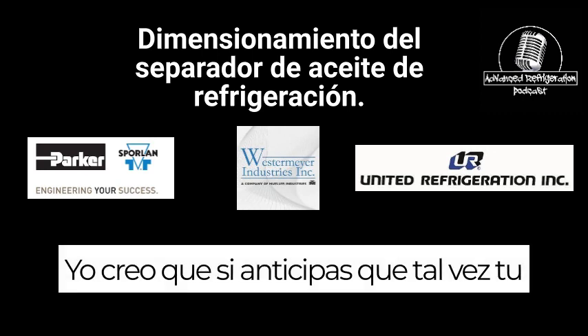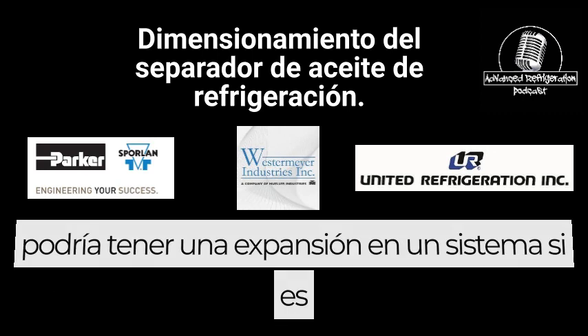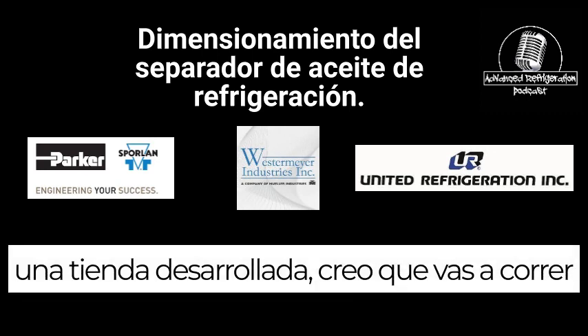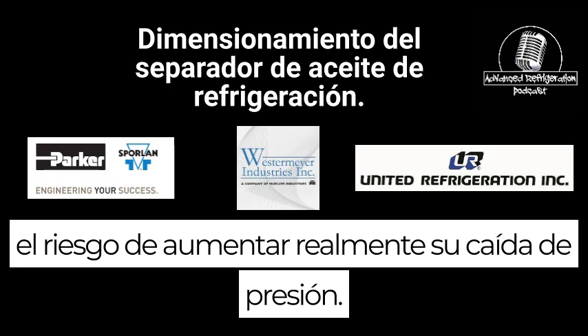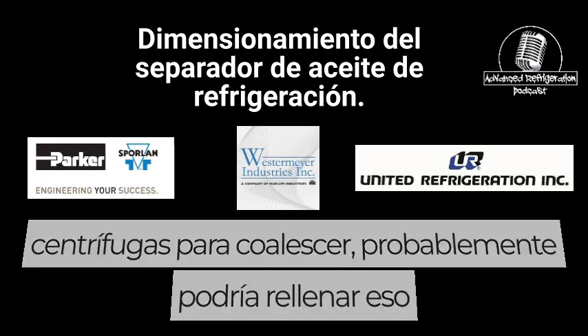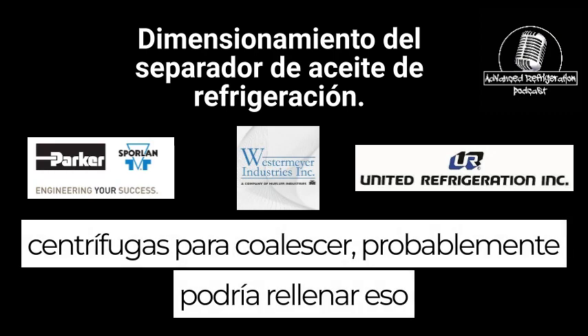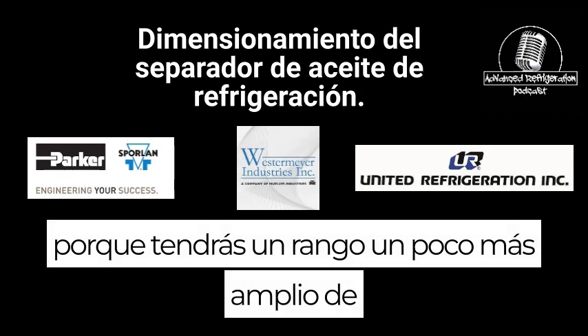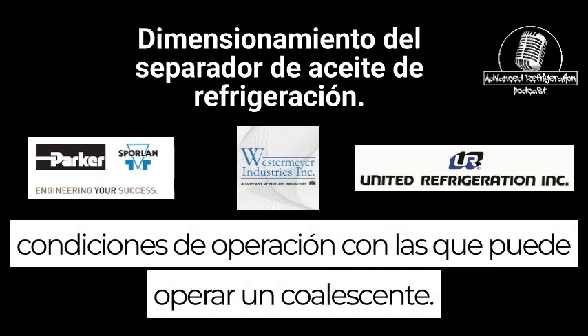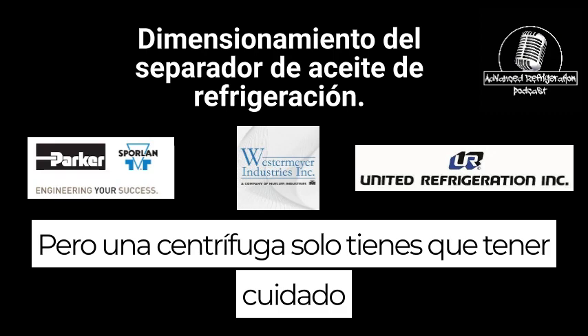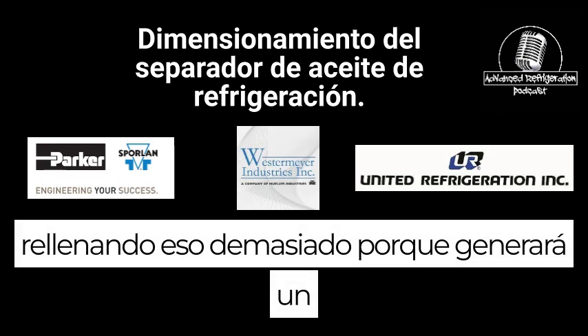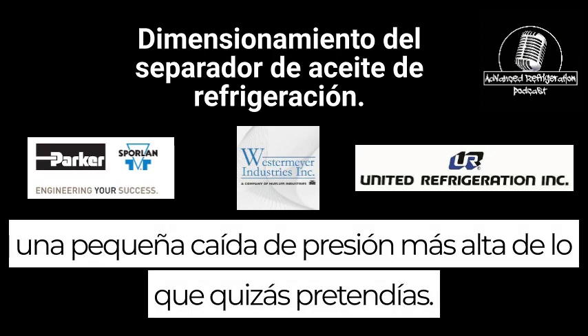I think that if you anticipate that maybe you could have an expansion on a system, if it's a developing store, you're going to run the risk of really increasing your pressure drop, because we're talking about centrifugals. For coalescing, you probably could pad that because you'll have a little wider range of operating conditions that a coalescing can operate with. But with a centrifugal, you've got to be careful padding that too much, because you will generate a little higher pressure drop than maybe what you intended.